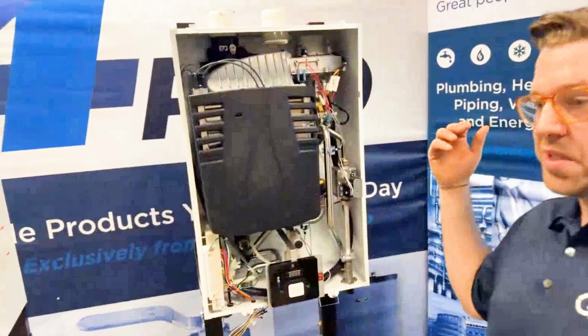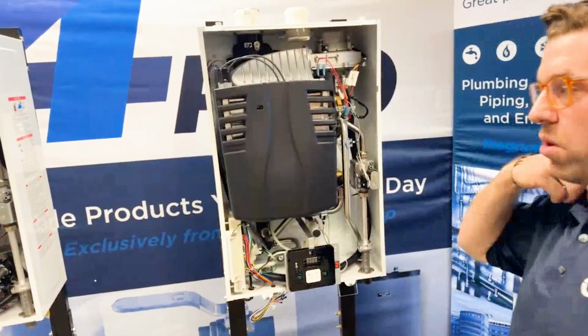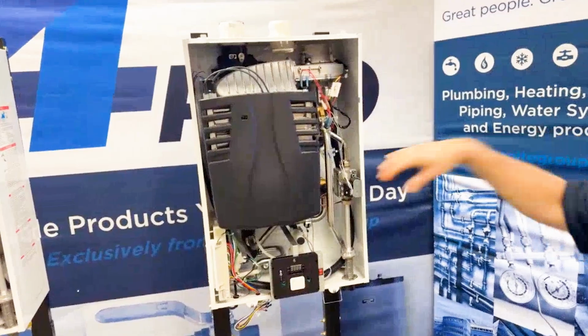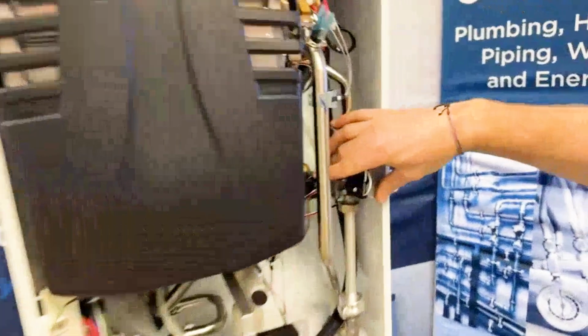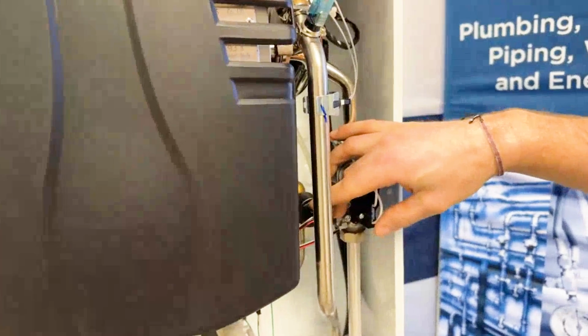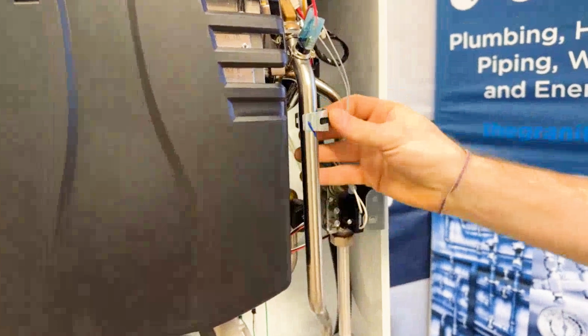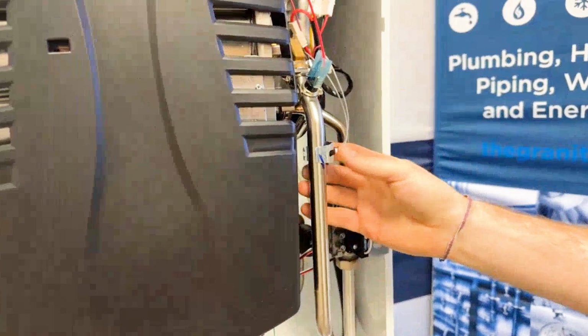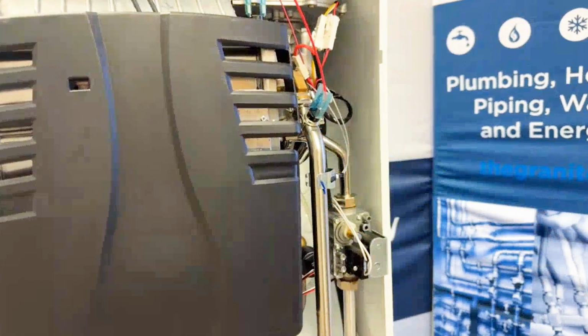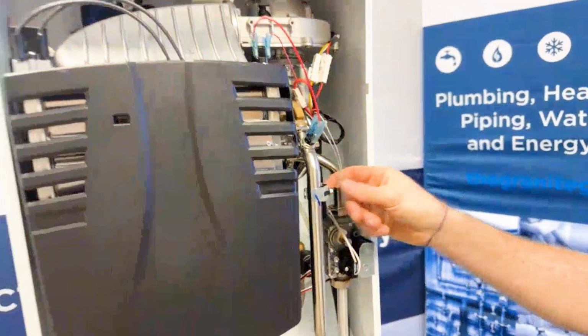Additionally, let's talk about some sensors on both of these boilers. Here's the pressure sensor on the heat only. That's going to be the only wet sensor on this boiler. Everything else is going to be located on the outside of the piping. So all of your temperature sensors, again, are located on the outside of the piping.